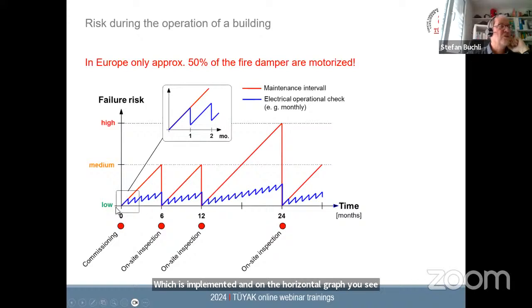So usually after commissioning you have like 2 6-month cycles where you have to do an inspection, usually on site. That's in most countries it's like this. And then after 2 successful periods of 6 months, you can expand this cycle to 1 year. So annual visual inspection is quite common.